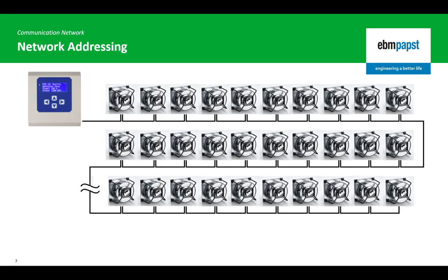The MDC controller has been configured to be compatible with the standard communication settings for all EBM PAPST Modbus-enabled fans. The MDC controller can be used on a network of up to 100 fans, and once the physical layer of the network has been installed and the fans and controller have been powered up, we can start the process of addressing the network.